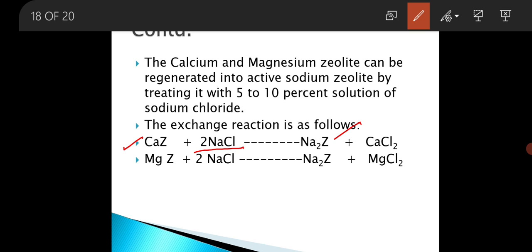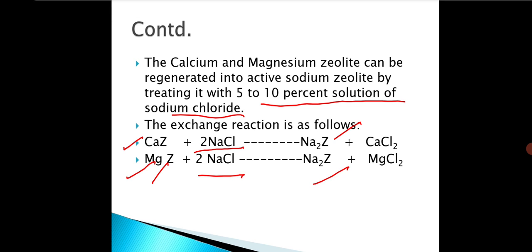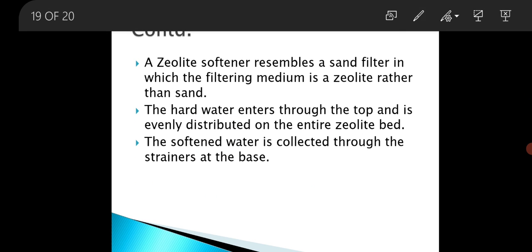Similarly, this magnesium zeolite — the used zeolite — when it reacts with a 5 to 10 percent solution of sodium chloride, it will regenerate the sodium zeolite. A zeolite softener is just like a sand filter in which the filtering medium is zeolite rather than sand.